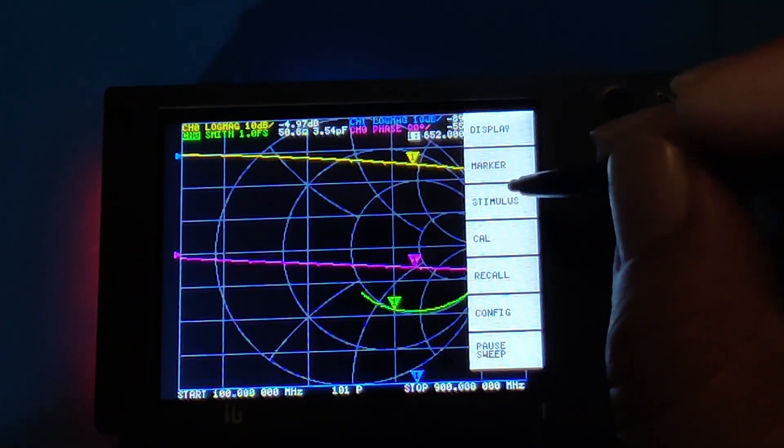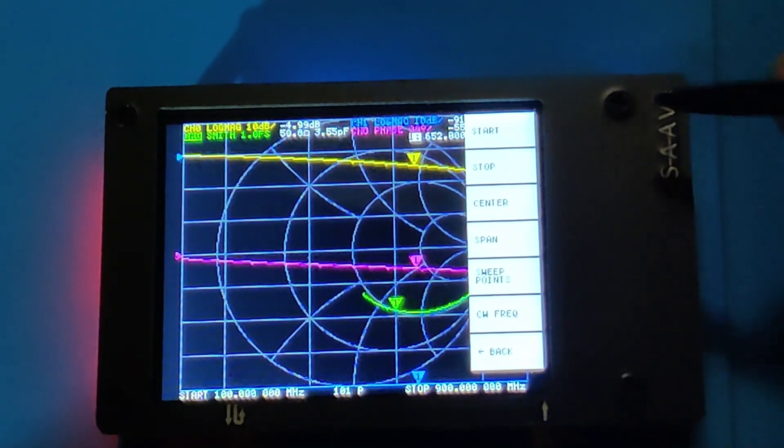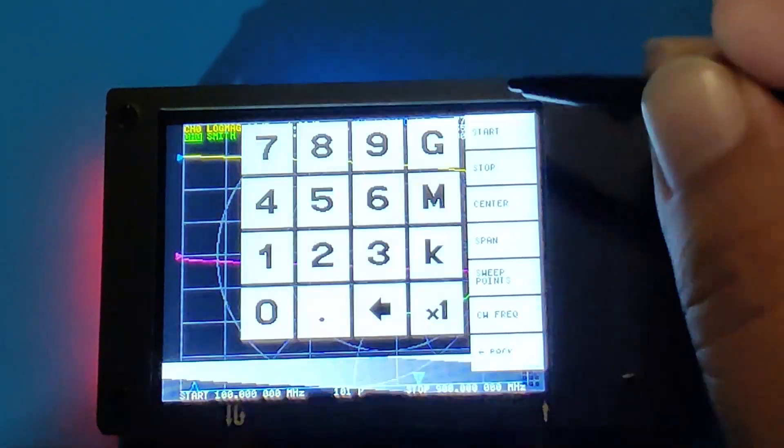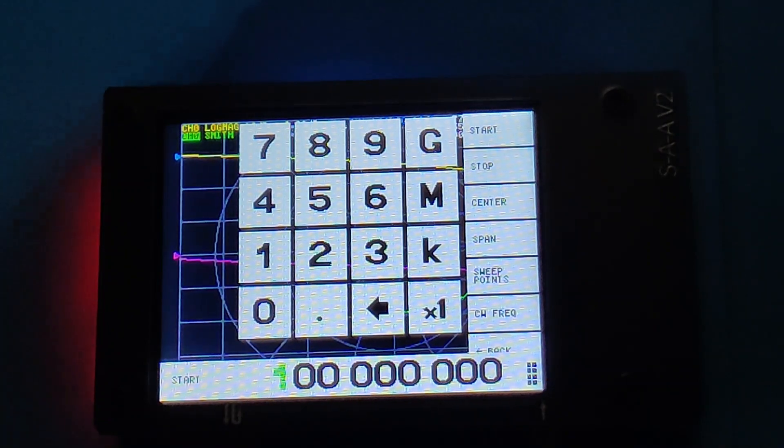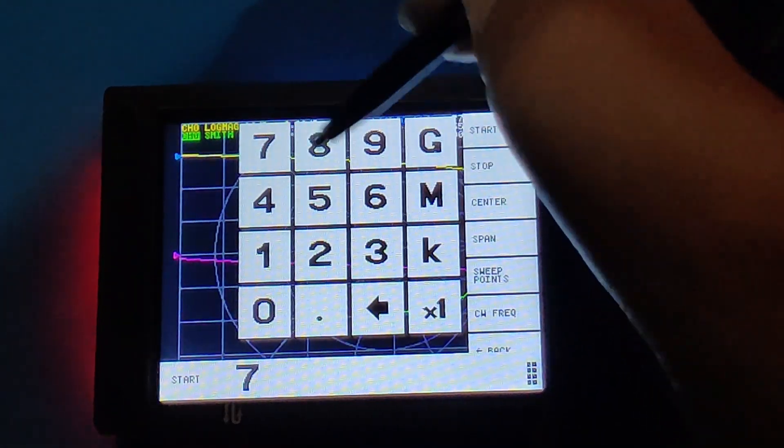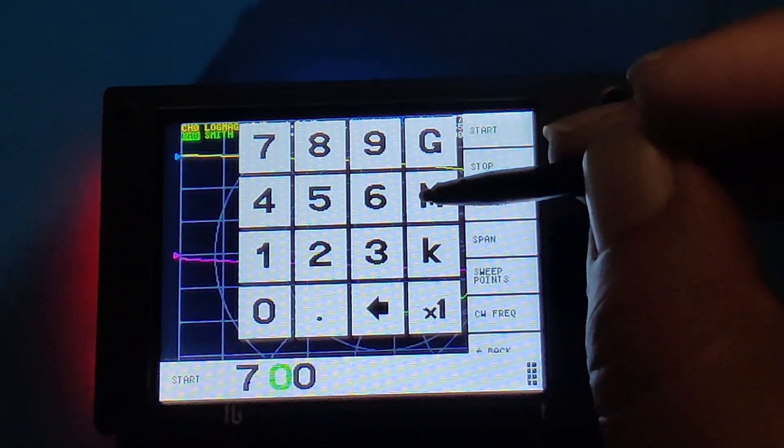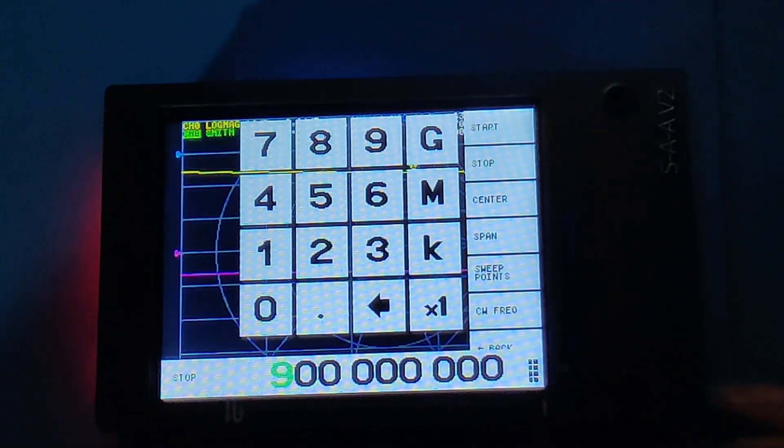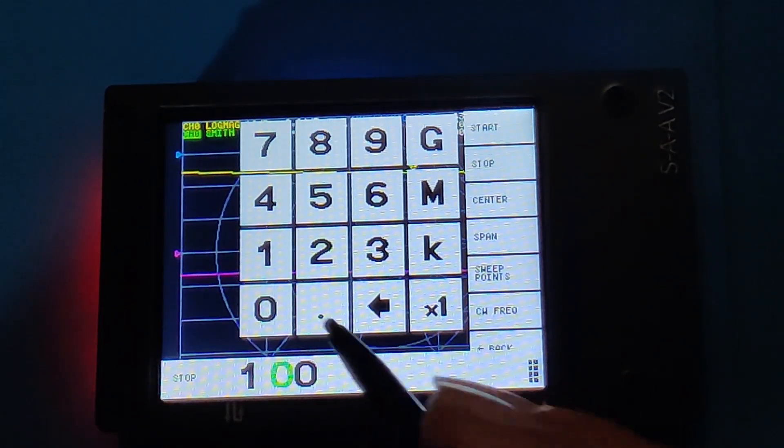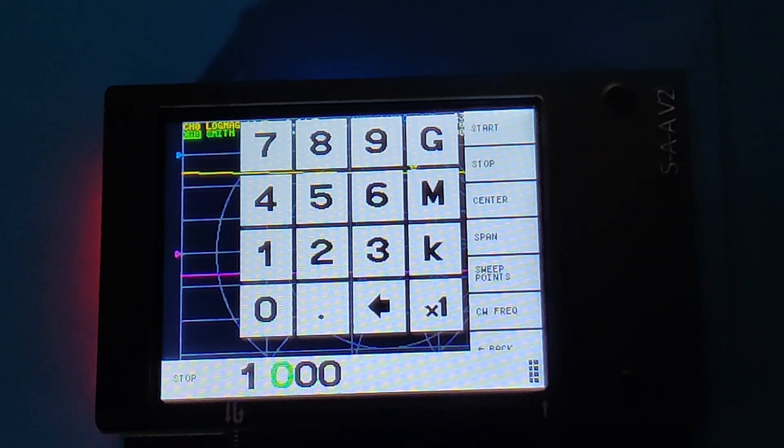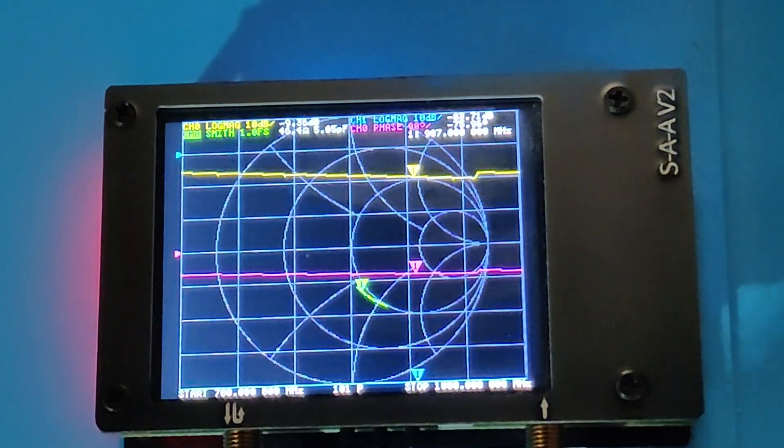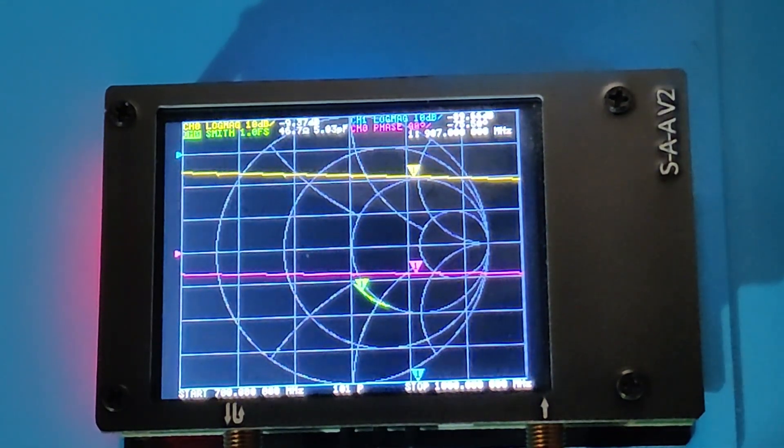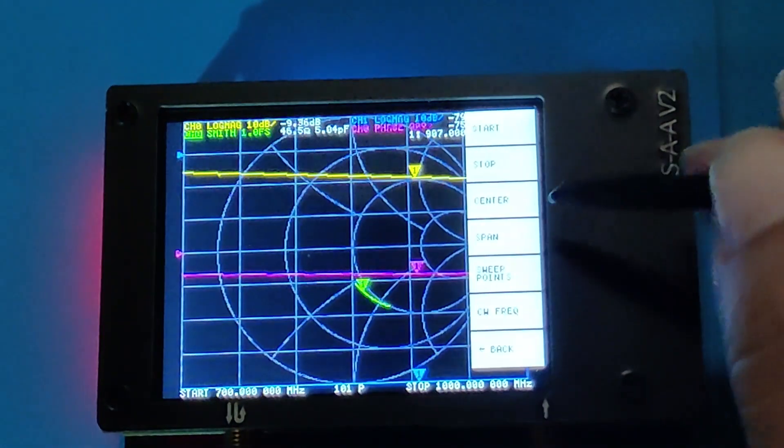With the menu, click on stimulus. After stimulus, I click on start and enter 700 MHz as the start frequency, then click on stop and enter 1000 MHz as the stop frequency. With this, I am setting the sweep range of the VNA. At the bottom of the VNA screen, we can see the start and stop frequencies we just entered into the system.